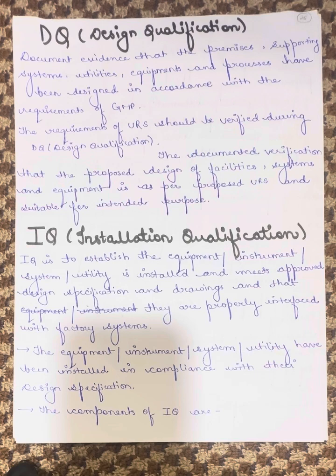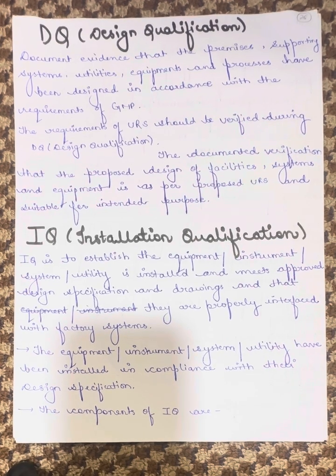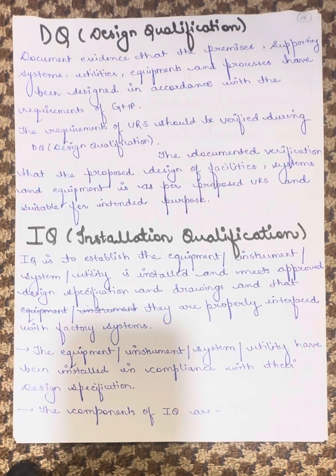IQ stands for Installation Qualification. It is to establish that the equipment, instrument, system, or utility is installed. The components of the equipment, instrument, system, and utility have been installed in compliance with the design specification. This includes supporting utilities, major components and accessories, verification of MOC, verification of process control instruments, identification of safety features and identification of SOPs.